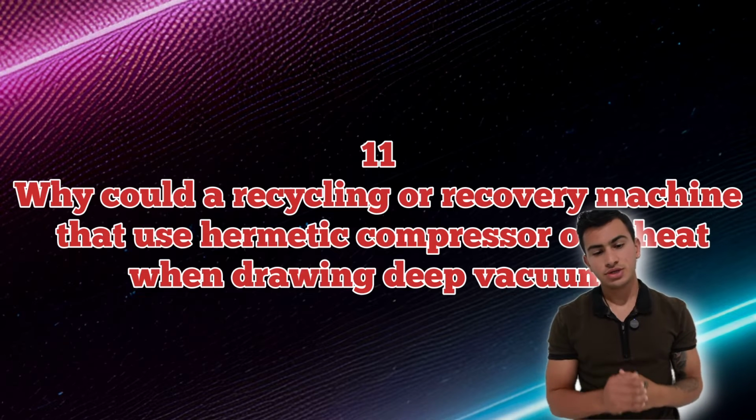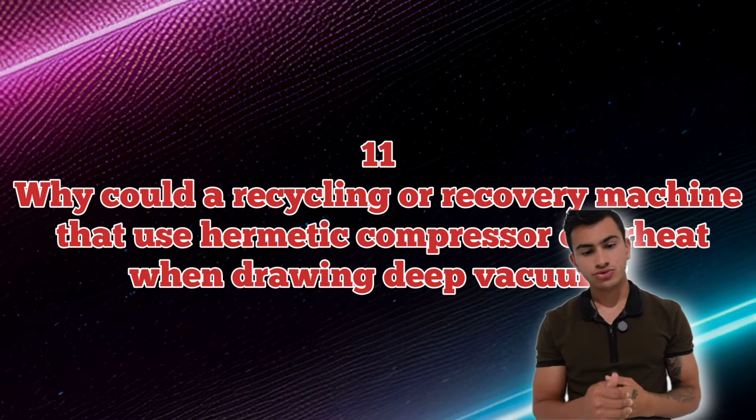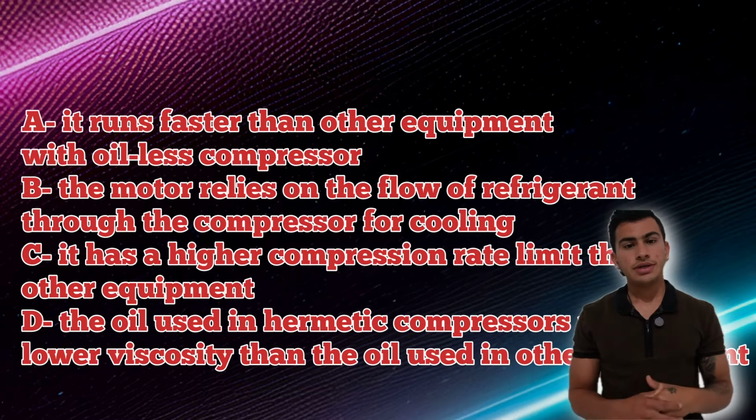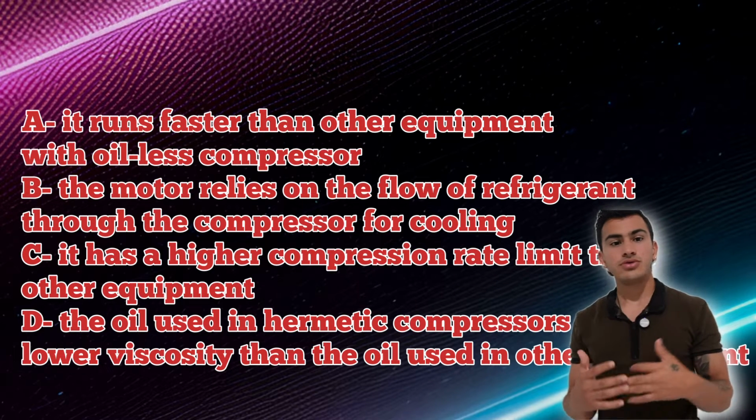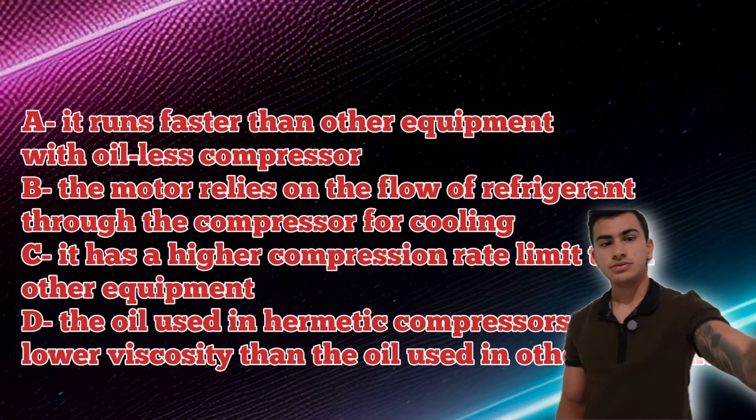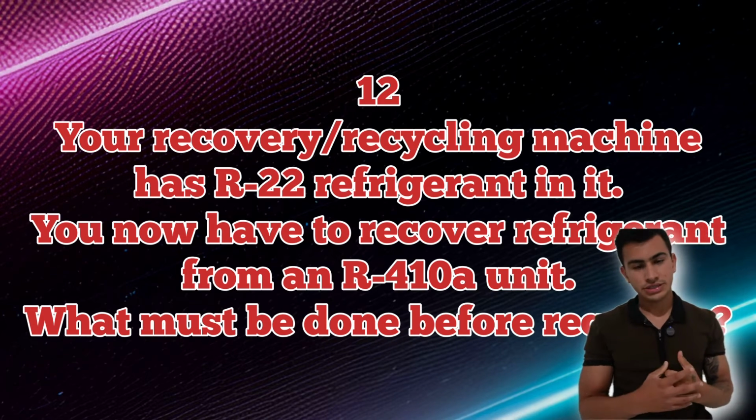If a hermetic compressor overheats when drawing deep vacuum, it is because the motor relies on the flow of refrigerant through the compressor for cooling. So for this answer is simple.